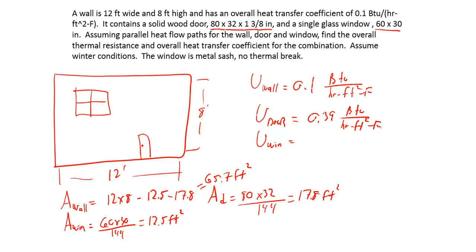That's for the door. For the window, same deal. You go to the single glazing all the way to the top on page 144, Table 5-5A. This window should find an overall thermal conductance of 1.27 BTU per hour foot squared Fahrenheit.